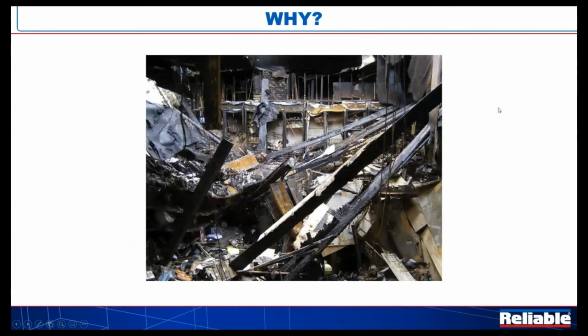And then the fourth reason, at least that I came up with, and there may be more, building collapse or structure collapse, right? We all know what happens when steel heats up. It loses its strength and it is prone to collapse. So this could either be building structure or the supports underneath a tank or underneath a pipe rack or a conveyor or anything like that. So we've got to protect those supports to maintain the integrity of whatever those supports are holding up.